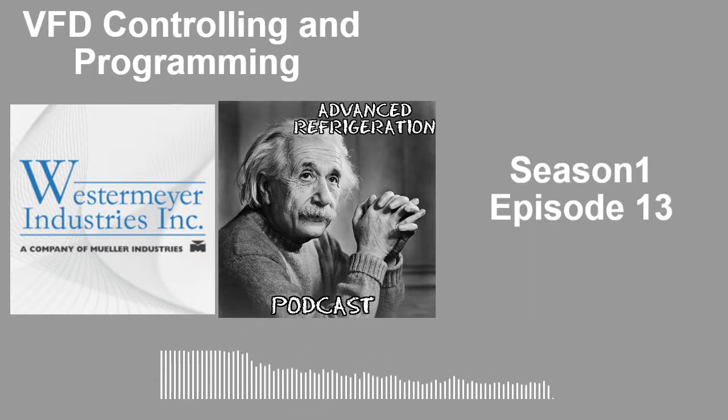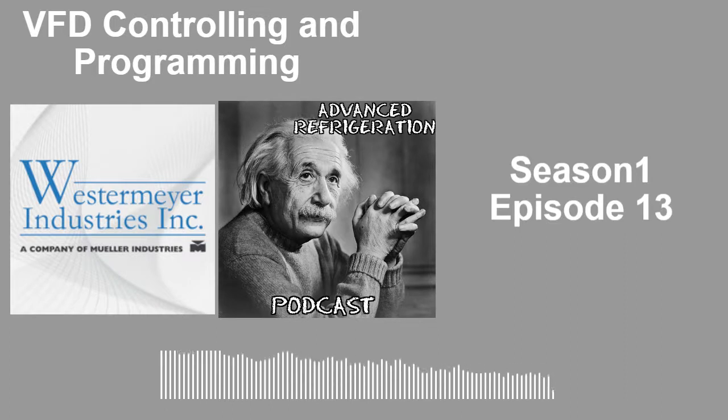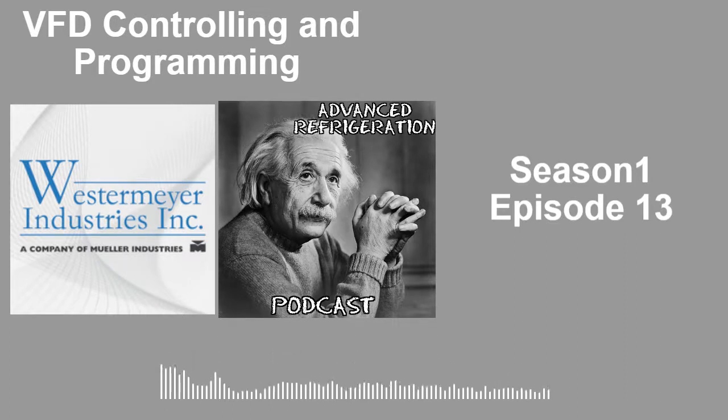Same thing, you just got to watch, like if the drive isn't working and everything's down. If your discharge transducer shorts out on a Novar store, they're taking it off the CCM, the condenser control board, and you go up there and you got no 24 volt DC power feeding that transducer, and you're not getting the signal supply or ground back, that drive won't work because it's not going to see any pressure. So that's just one thing to be aware of.